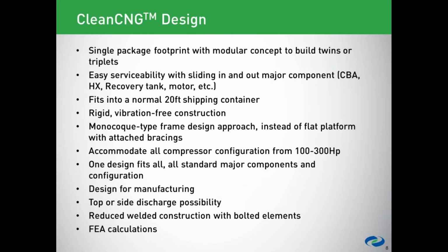Easy serviceability with sliding in and out major components. So the unit you will see has huge doors on the back and the front that open up. It has a fully covered and protected service walkway that takes you right into the unit, fully lit and safe from the weather, that allows access to the back of the CBA and back of the heat exchanger into all electrical, so you don't have to have a tent and dry off a panel if you're in the rain. It fits into a normal 20-foot shipping container.